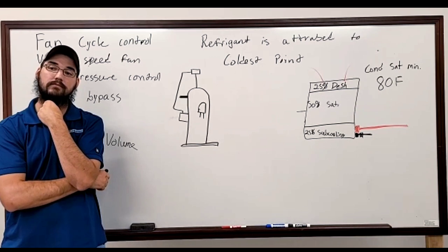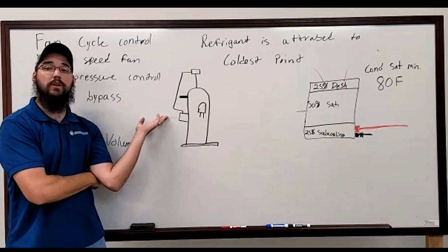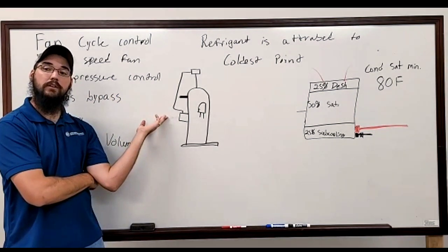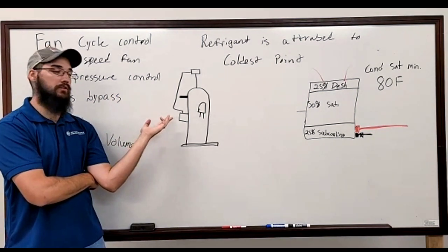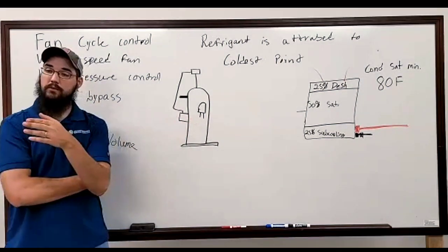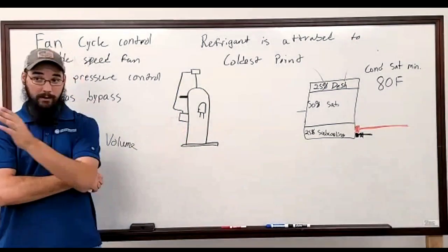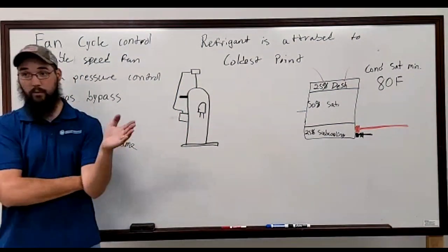So it's kind of flashing as it... So you still have enough load happening on your evaporator that it is still controlling the motor temperature. But you just took half of the load off of that compressor. Your amps go from 8 to 4.